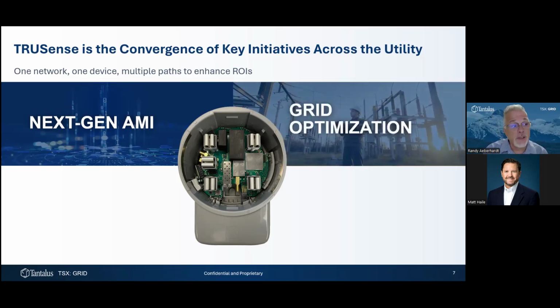With TRUSense, you can now start doing a lot of grid optimization with the granular data coming out of this device, which measures power quality, power factor, volts, kilowatts, reactance, resistance, impedance. This device supports 12 configurable, or utility-configurable, channels of data recording that can be delivered to your SCADA system, your ADMS, or your control systems, allowing you to operate the grid in real time—optimizing voltage output, power factor, and load balancing in real time.